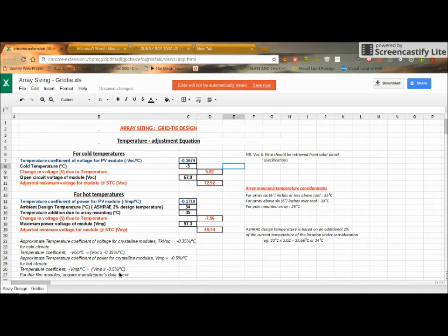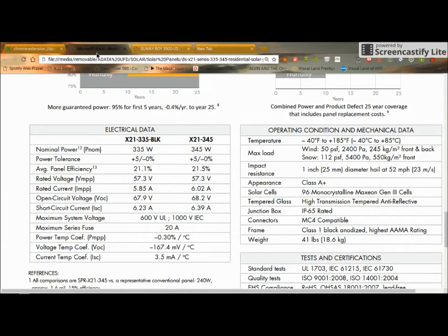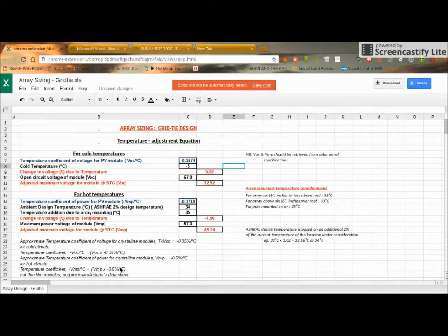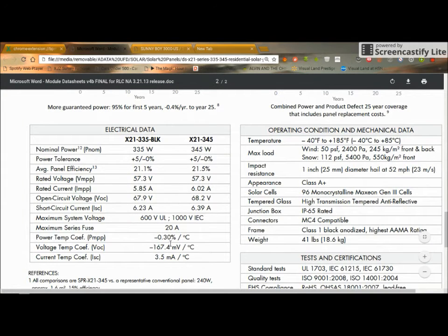This was based on a book, a range here, but for the specific module that we're using, the manufacturers have given us the more accurate figure. What the book gave us is a range that can be used here. So since we have the actual specification here, we would put the 0.3% or 0.003 per degree Celsius rise.